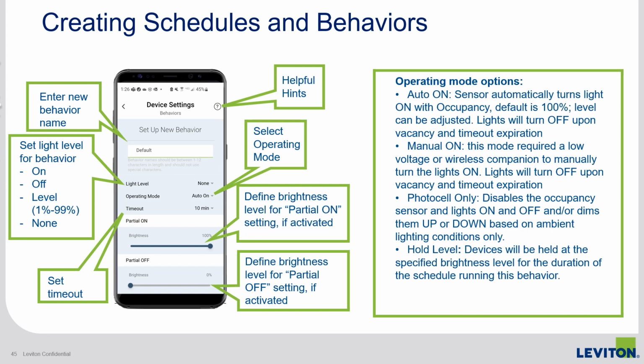In this mode, the lights will turn automatically on with occupancy. The default is 100%, but the level can be adjusted with the partial on level. The lights will turn off upon vacancy and once the timeout expires. Manual On. To select Manual On, the room controller must be connected to a low voltage keypad or companion switch or dimmer, which is required to be pressed to turn the lights on. The lights will turn off upon vacancy and once the timeout expires.